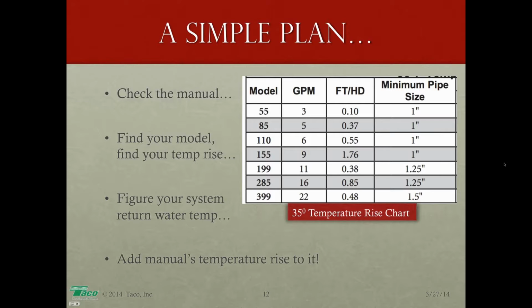Some people prefer to say, hey, I don't care what happens, you've got to scrub the heat exchanger and keep flow up and going. Different schools of thought. What does your boiler manufacturer say? Really in this case, that is what you should do, because they have the final say. All right, from Dan: GPM flow in the boiler and distribution flow should be the same. If distribution GPM is higher than the boiler loop GPM, then recirculation will take place. I think as we see here, Dan, not necessarily.